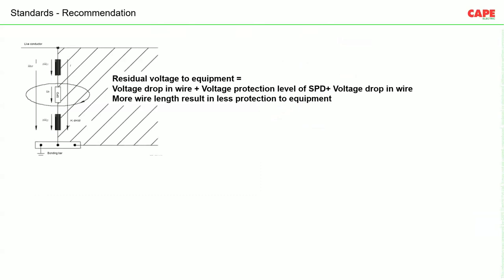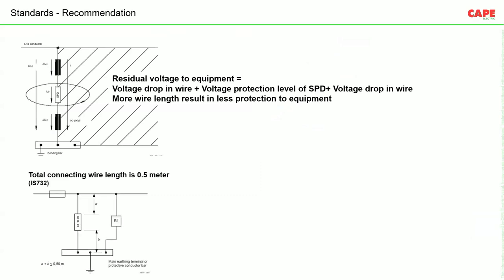So now what does the standard say about this? The standard first talks about the residual voltage to equipment. That means the effective voltage protection level at the equipment will be the voltage drop across the wire plus the voltage protection level of the SPD plus the voltage drop across the wire. I am going to explain this in the next slide. As per IS 732 and NBC 2016, the maximum acceptable wire length across SPD is 0.5 meter. That means if you see a connection, this is your main breaker and this is the SPD connected between earth and this line. Let's say it's a line. So from line to SPD, there will be one wire.